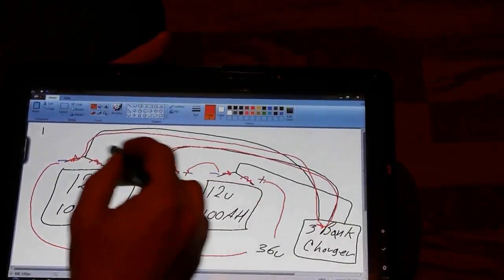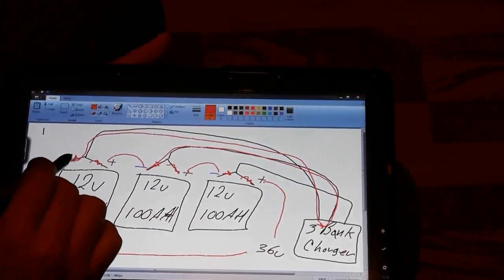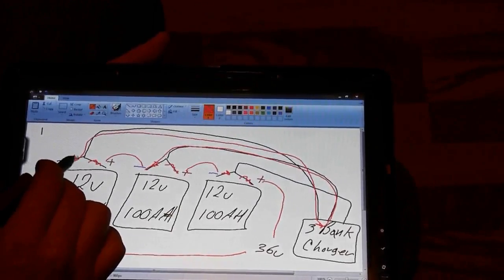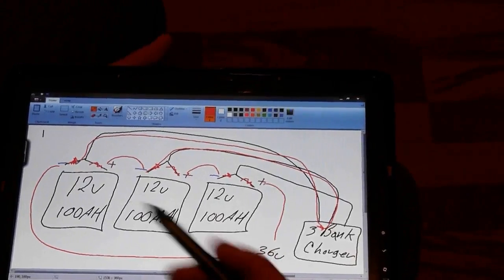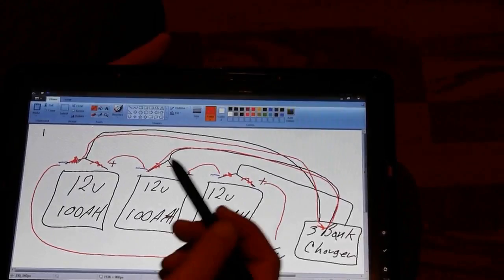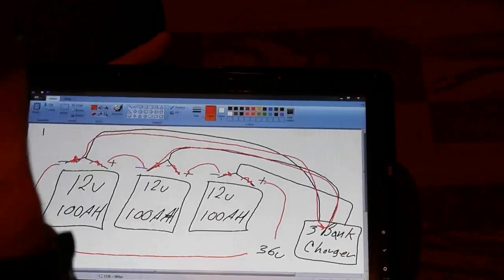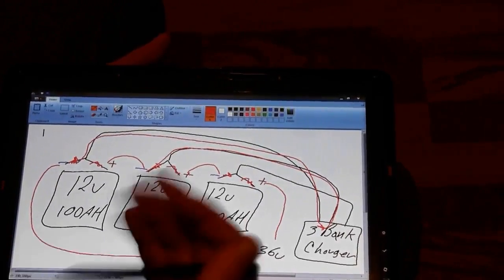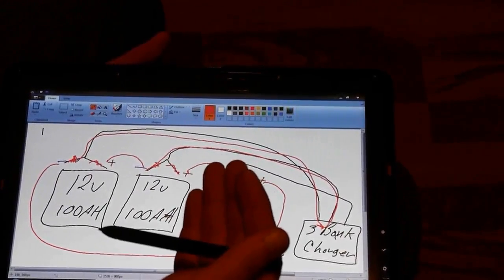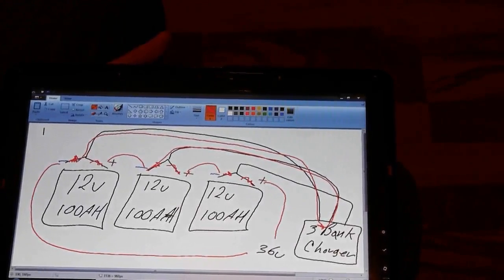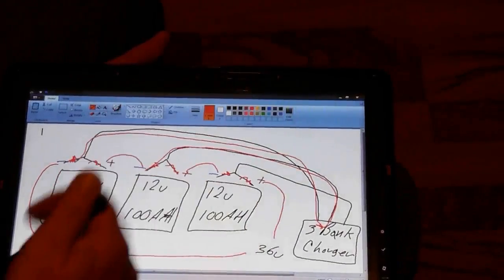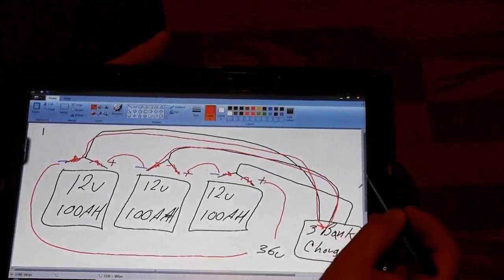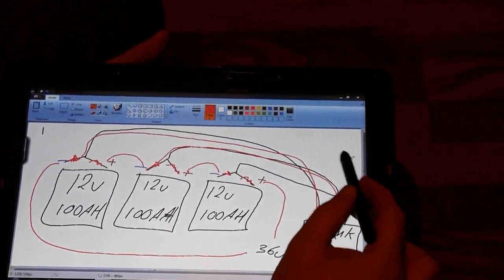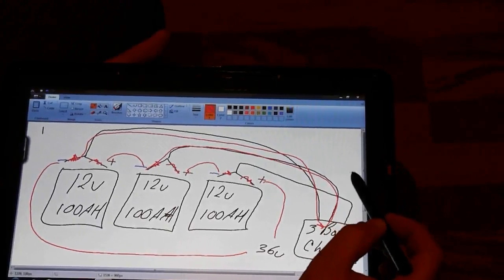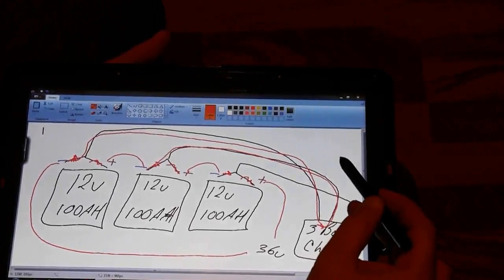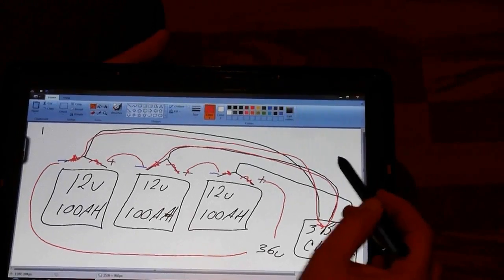His charger actually smoked and burned up the ground wires and stuff. I know manufacturers don't include a fuse on the ground, but from a safety aspect, I think it's a good idea - I think manufacturers should include that. It's a standard procedure in the industry I work in that anytime you take a ground directly to the battery, instead of to the chassis, that ground is always fused. That's because, for example in a car, if the negative terminal connection from the battery to the chassis came undone, then all the current flow would be through that ground - that's why you want that fuse there.